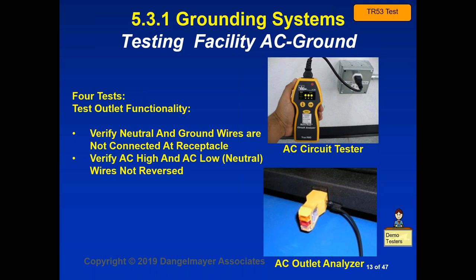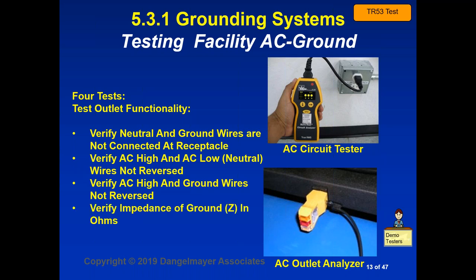You want to verify that your AC high and AC low or neutral are not reversed. You want to verify that the AC high and ground wires are not reversed. That would be very bad. And finally, you want to verify the impedance of the ground in ohms. This is a test that the meter you see in the upper picture will be able to do for you. If you don't have that meter, you'll need to do a different test. I'll show you a picture of that in a moment.